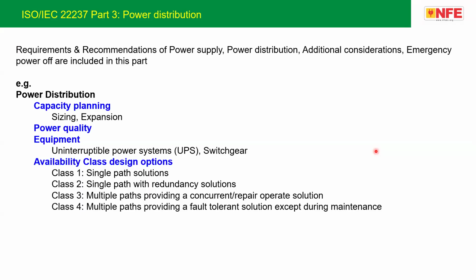Now, when we move to the availability class design option, it will be the same in the power distribution system as for the power supply. There are four classes: class 1, class 2, class 3, and class 4. As I already explained, class 1 is a single path, the second is a single path but with redundancy, class 3 is multiple paths with a redundant source, and the fourth is multiple paths with additional equipment also. So it will be equivalent to tier 4.